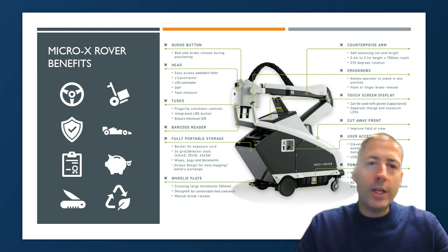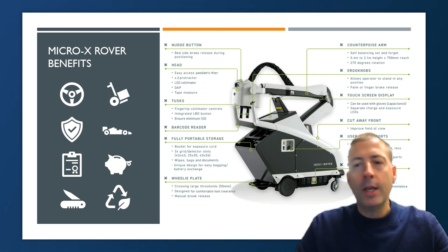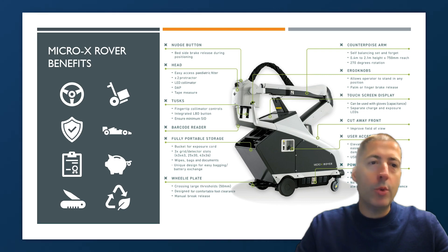The image quality is really equal to that of full-room devices, which I'll show you in a second. It's very cost-effective, and there's also the environmental impact to consider — the Micro X Rover has a lower energy requirement than full-room systems, which is really important in this day and age.